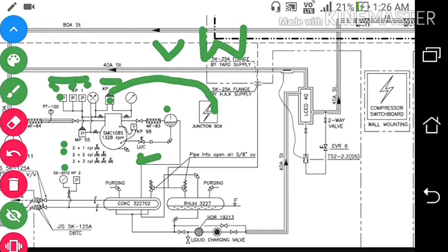Now in the compressor, the valves are plate type suction and delivery valves whose large diameter and small valve lift offer the least resistance to the flow of refrigerant gas. So gases from the evaporator pass through the strainer housed in the suction connection to the machine. So in the suction of the compressor we have a strainer over here. And in this figure you can see this is the expansion type of pipe over here.